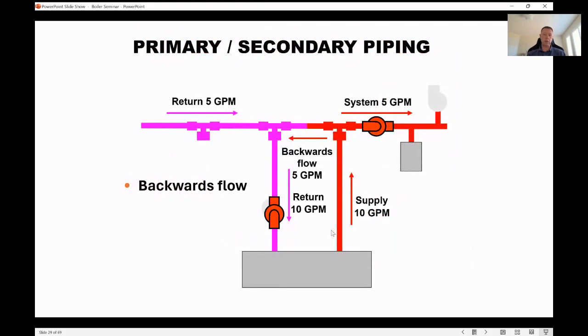So here, let's take a look with some light math for you. Let's say you have 5 GPM in this system loop and you have 10 GPM in your boiler loop. Well, your return is 5 GPM. 10 GPM goes into the boiler, 10 GPM comes out, 5 goes to the system. The other 5 reverses back and goes directly back into that boiler, right? So you're reheating that water you've already heated, which is less efficient. And what you can find is you can potentially get into a cycling situation.